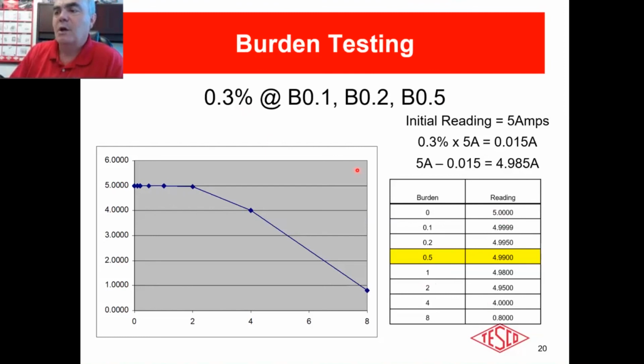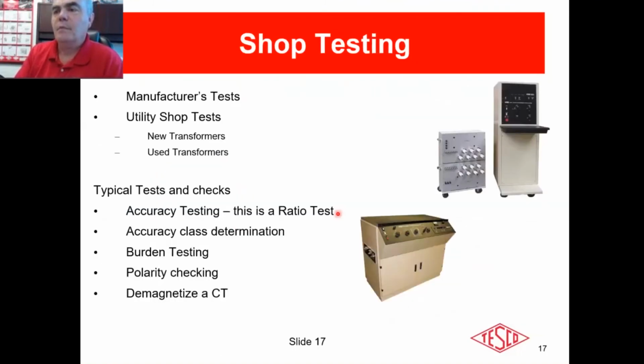99.7, all right? So when I drop below 0.5, okay, I start to drop off, and you can see it right here, but I don't really go out of accuracy for a little while. But notice what happens once I start putting on 2 ohms, 4 ohms, and 8 ohms worth of burden. The accuracy drops way off, way off, all right? And again, we'll come back to that in just a little bit. So how do you test in the shop? I'm going to digress for just a second here.